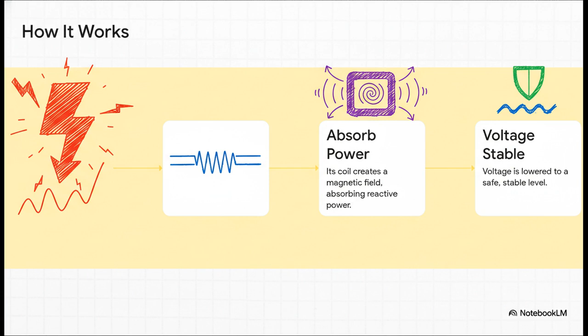All right, so let's do a quick play-by-play. Step 1: that excess capacitive energy makes the voltage on the line start to climb. Step 2: the shunt reactor, connected in parallel with the line, gets to work. Step 3: its massive coil creates a magnetic field, which gobbles up all that reactive power. Step 4: the voltage drops back to a safe, stable level. Problem solved.